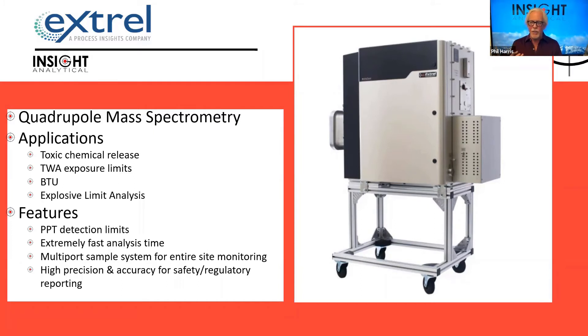We see these being used on flare gas for BTU analysis. We'll see these being used across a number of different process applications. We're very common in ethylene plants as universal analyzers. PyGas samplers are often put in front of a mass spectrometer to keep all that particulate and steam away from the mass spec.